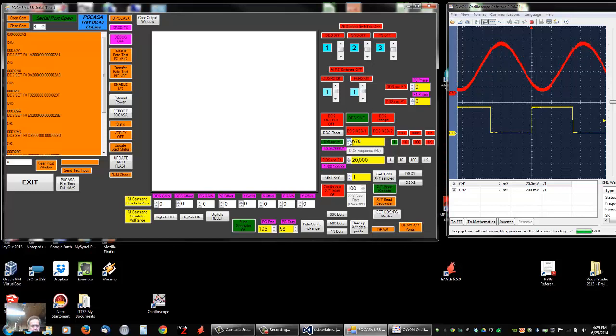So, what I got here is I got my output waveform set at 59.9 hertz. My pulse generated frequency, it says 195 there in the bottom, but like I say, that's just a delay number. And what the actual frequency is 59.85 hertz. So it's triggering off the bottom one, but reading both of them. So the top one is a tenth of a hertz off, which means about every 10 seconds that wave is going to complete one cycle across the center line there, because they're 1/10 of a hertz off, and that's fine.